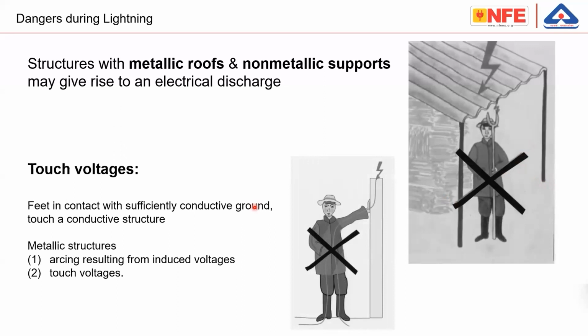Also, touch voltage: imagine partial lightning current, not the full lightning, flowing through some metallic objects. Even in a good building with protective equipotential bonding, probably lightning current may be flowing through some of the metallic parts. If you are standing outside the building and touching one of these metallic parts, there is a chance of touch voltage. If you are standing inside a building with reinforcement, steel reinforcement, then this chance is nullified.